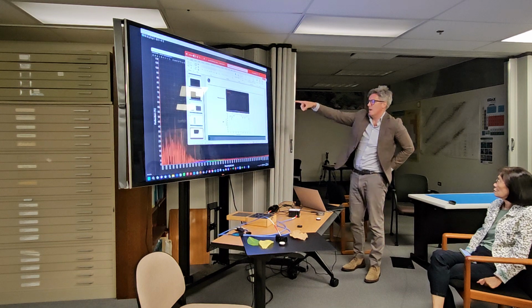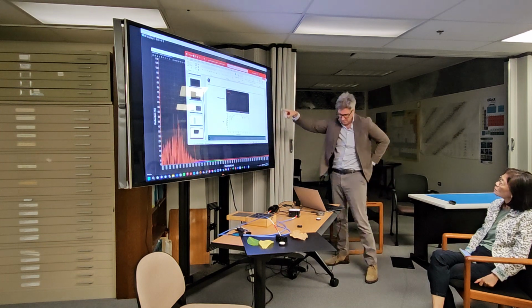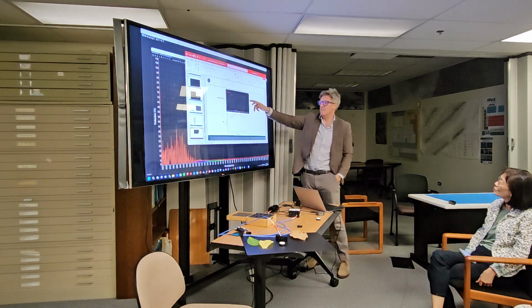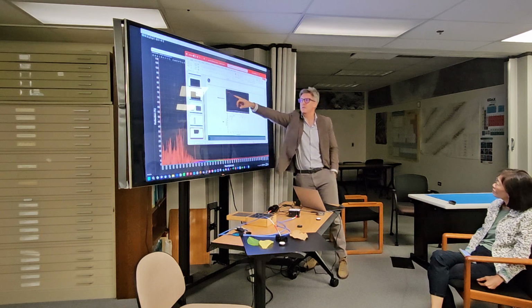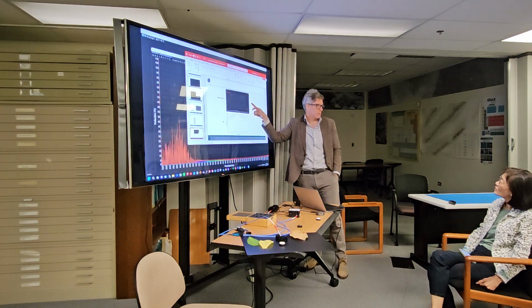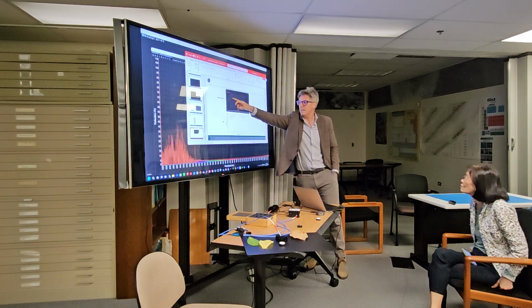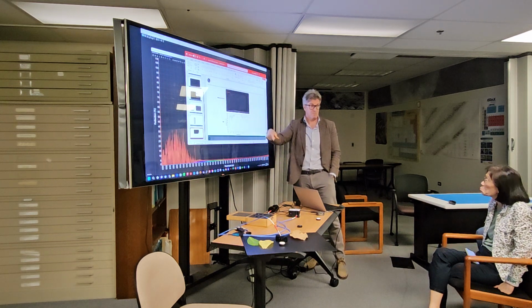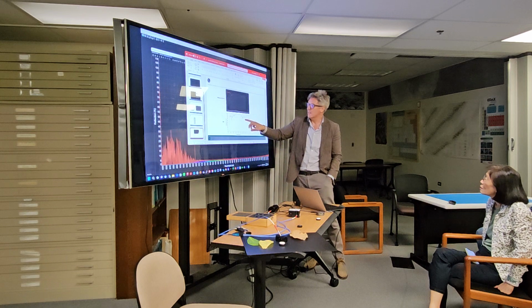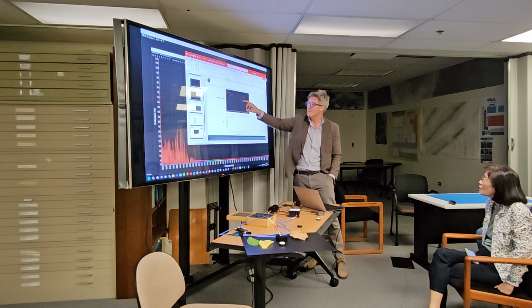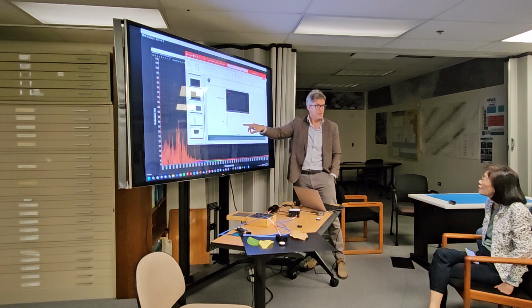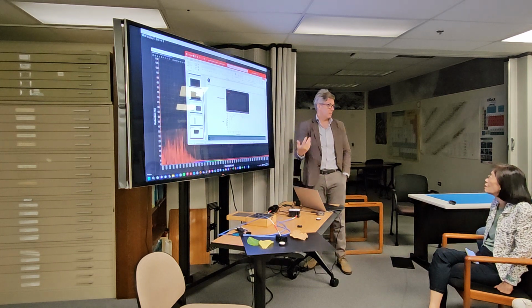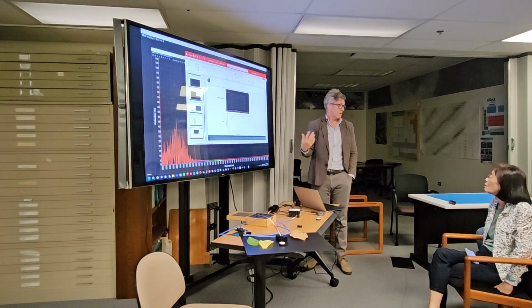So again, this was one that I made yesterday in my office. Same setup. This is the measurement of that target, and again, we've got noise here, so it's crap. But this is the measurement I made in the lab. This was the calibration measurement that they sent me when they sold me that thing. And you can see that this feature looks like this feature, and this feature looks like this feature, and this feature looks like this feature, right? So it's just telling me that the spectrometer is still healthy and still working.